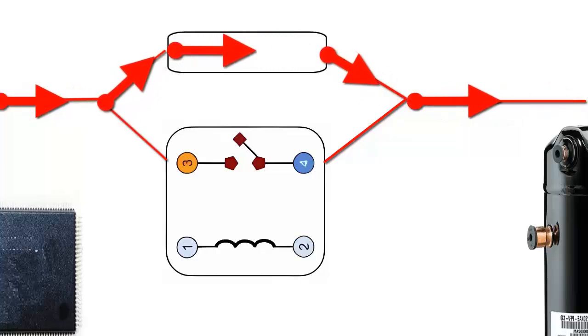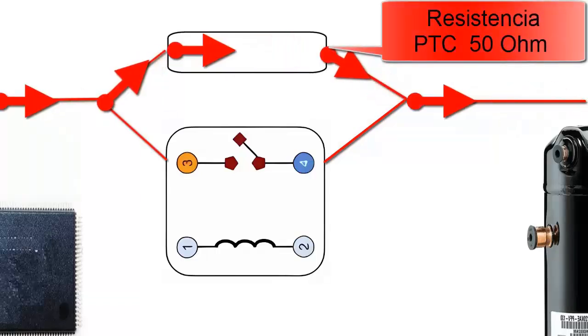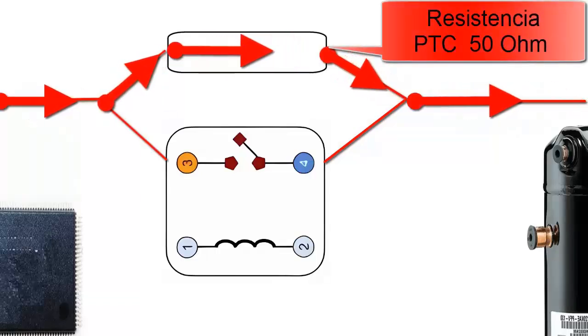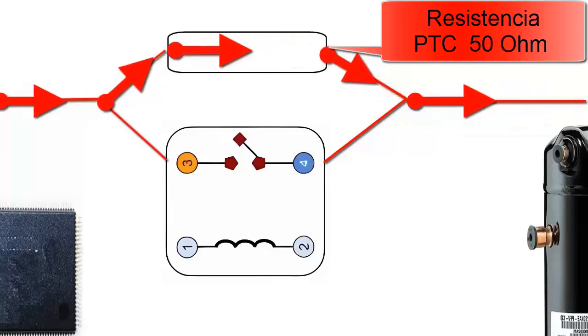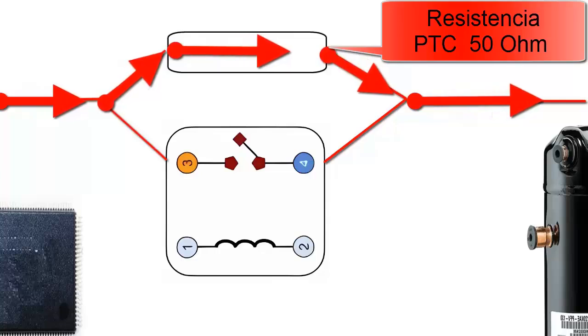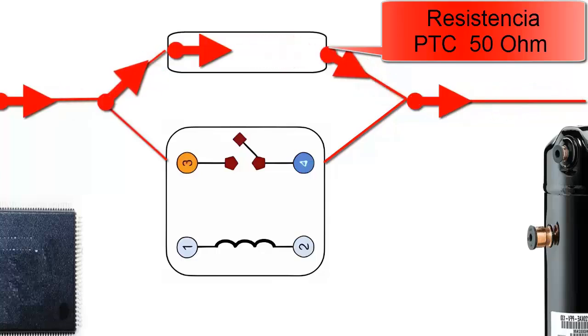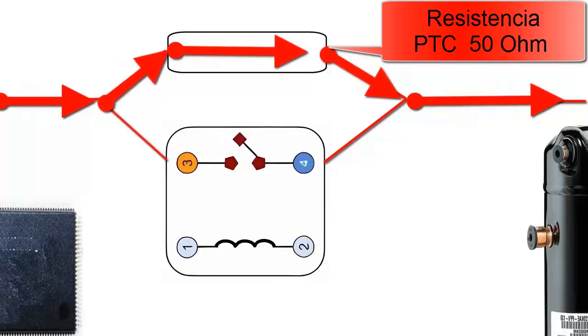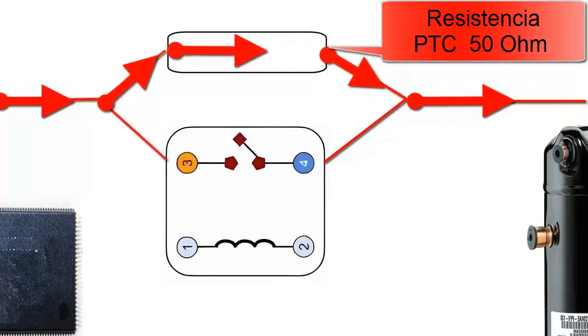As the unit starts up, this initial current flow increases the temperature of the PTC resistor to, for example, 45 degrees Celsius. Consequently, the PTC resistor now has an electrical resistance value of, for example, 50 ohms. This increase in the PTC resistor's value helps to further control the initial starting current.